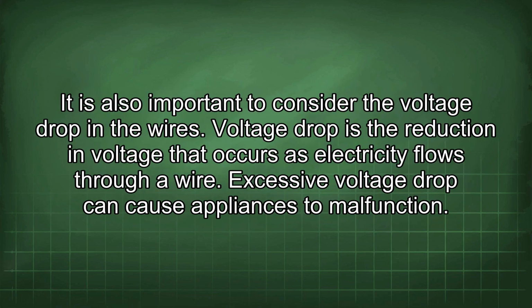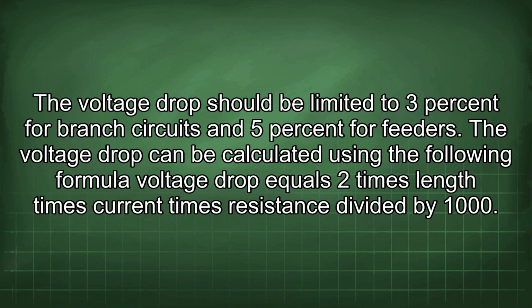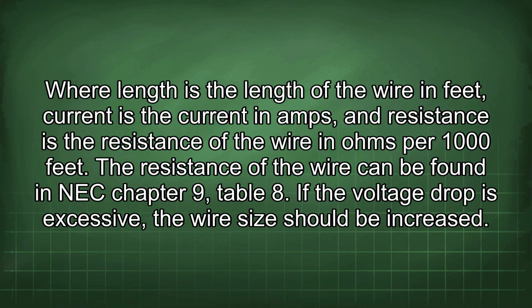It is also important to consider the voltage drop in the wires. Voltage drop is the reduction in voltage that occurs as electricity flows through a wire. Excessive voltage drop can cause appliances to malfunction. The voltage drop should be limited to 3% for branch circuits and 5% for feeders. The voltage drop can be calculated using the following formula: voltage drop equals 2 times length times current times resistance, divided by 1000, where length is the length of the wire in feet, current is the current in amps, and resistance is the resistance of the wire in ohms per 1000 feet. The resistance of the wire can be found in NEC Chapter 9, Table 8. If the voltage drop is excessive, the wire size should be increased.